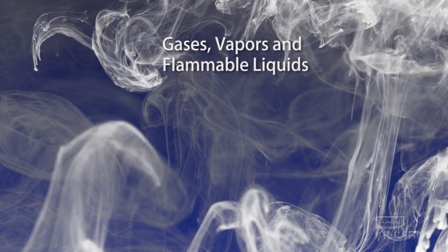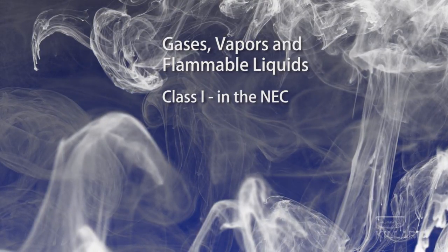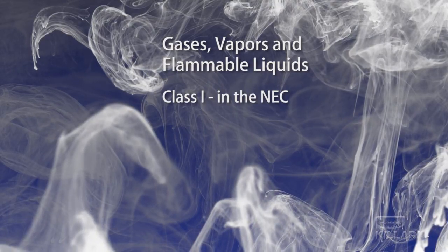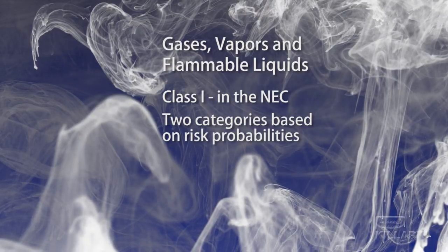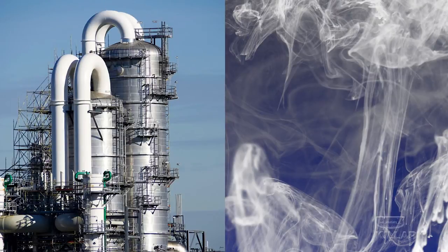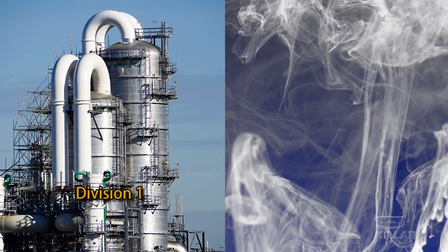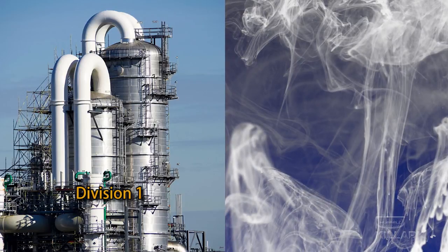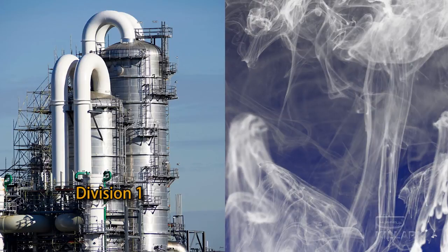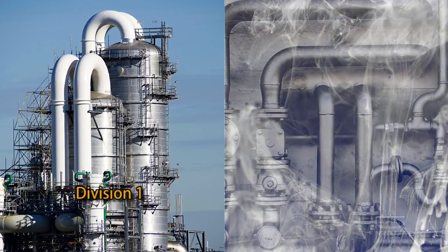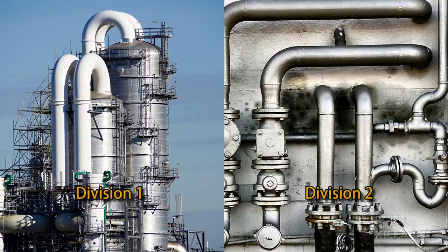Risk analysis involves measuring the prospect that there is sufficient flammable material in the atmosphere to create an ignitable mixture. Starting with gases, vapors, and flammable liquids, referred to as Class 1 in the National Electrical Code, the North American approach has traditionally divided the risks into two categories, reflecting the probability that an ignitable mixture could occur. The first, Division 1, includes locations where normal operations could permit the flammable material to form ignitable concentrations in the atmosphere, either some of the time or perhaps even all of the time. In contrast, Division 2 describes locations where hazardous materials are stored, handled, or processed in ways that are unlikely to create ignitable mixtures when everything is operating normally.